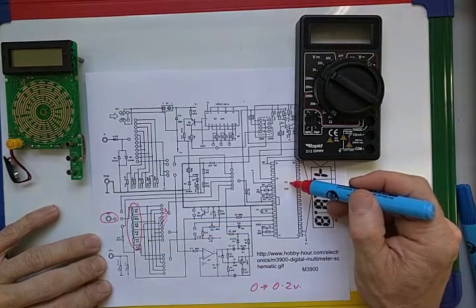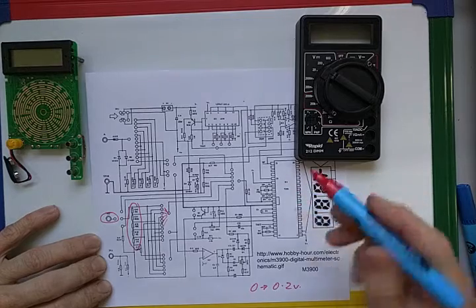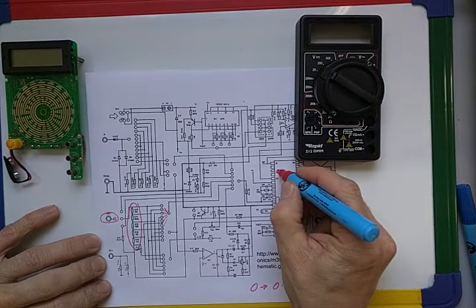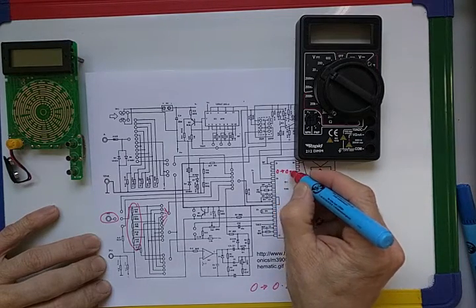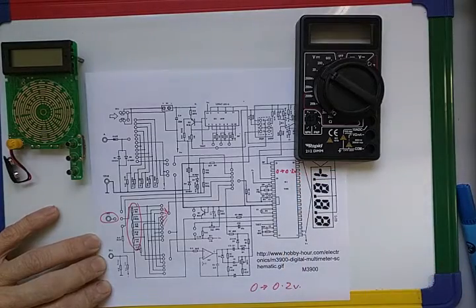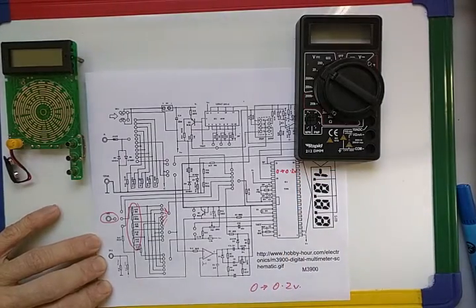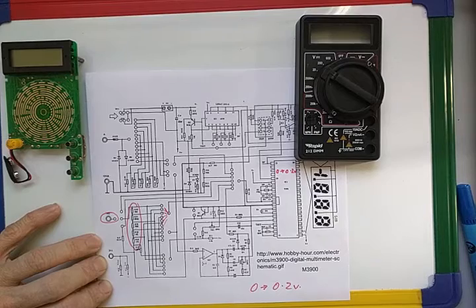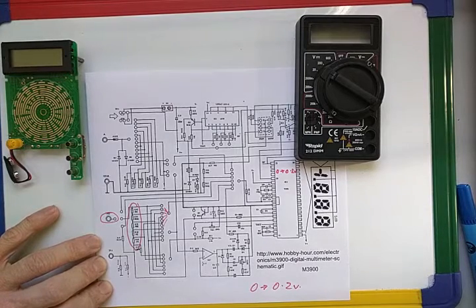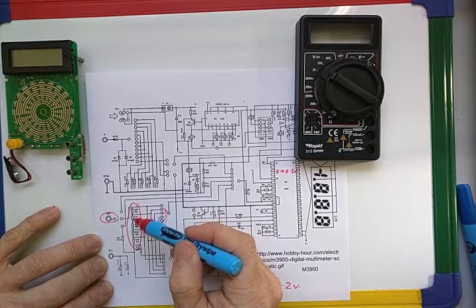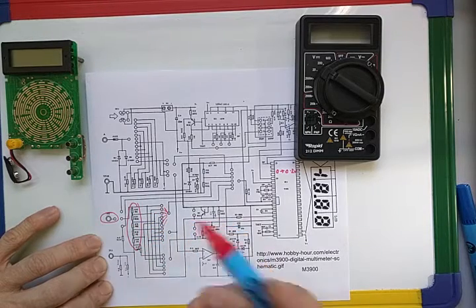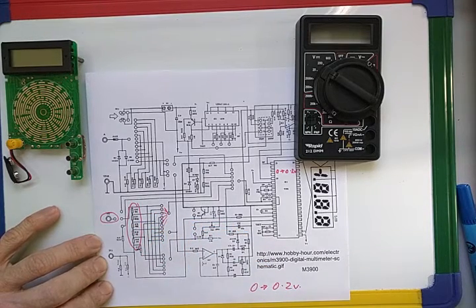The main IC inside this digital meter can only read inputs of 0 to 0.2 volts, and yet you want the meter to read 2 volts, 20 volts, and 200 volts. So essentially the voltage you apply gets dropped down in a ratio of sort of 10 to 1 or 100 to 1.